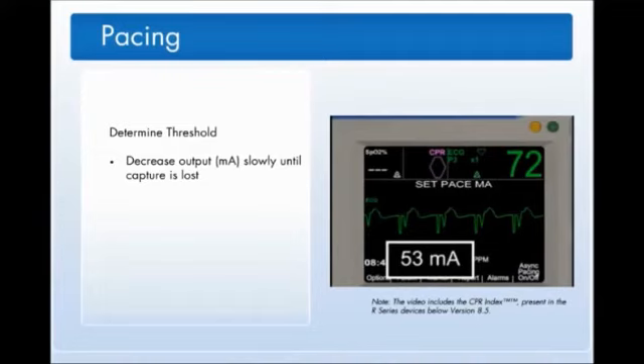Decrease the output slowly until you just lose capture, and then slowly increase it until capture is regained. This output is the patient's threshold. Once you have determined the pacing threshold, set the output to 10% above that threshold.